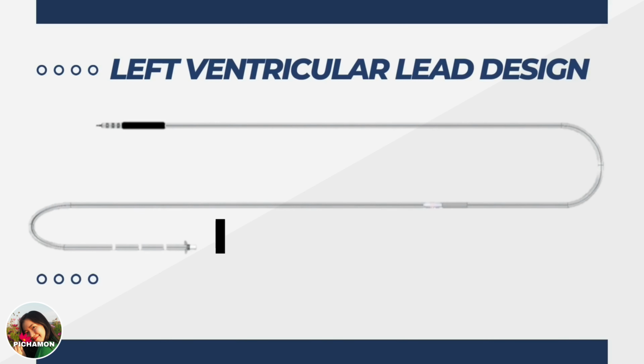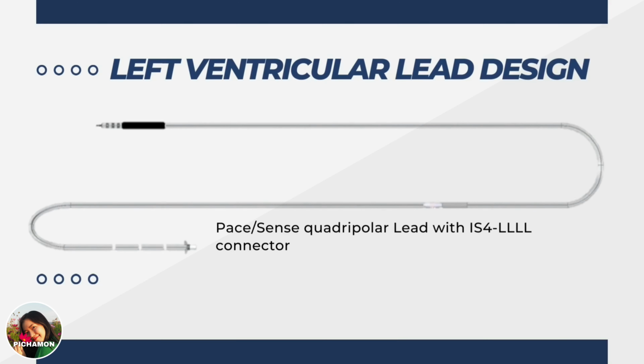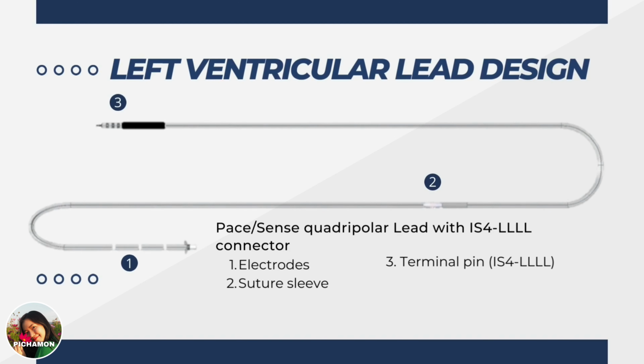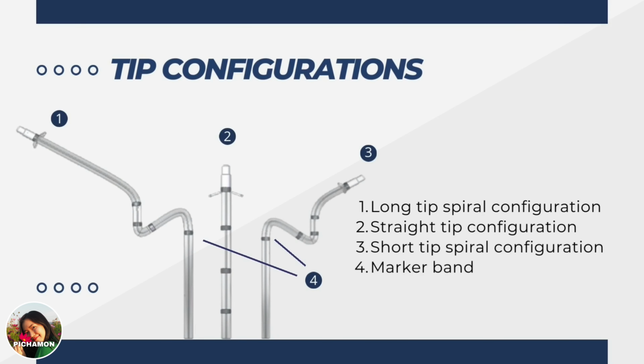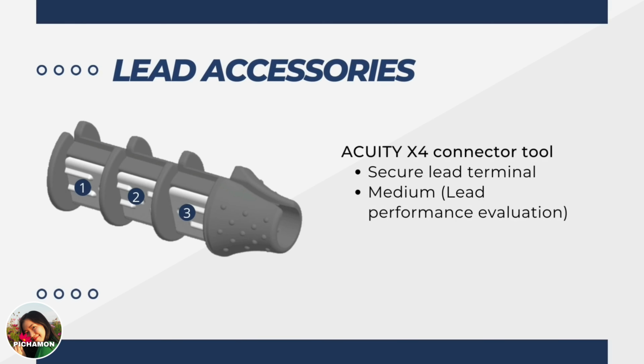The design of the left ventricular lead is based on a pacing quadripolar lead with IS4-LLLL connector. The four electrodes act as cathode and anode, except the distal electrode, which only acts as cathode. This lead has three tip configurations consisting of long tip spiral configuration, straight tip configuration, and short tip spiral configuration. The marker bands are only in spiral configuration. For lead accessory, the lead cap design is based on a ACUITY X4 connector tool to secure lead terminals during implantation and act as a medium during lead performance evaluation.